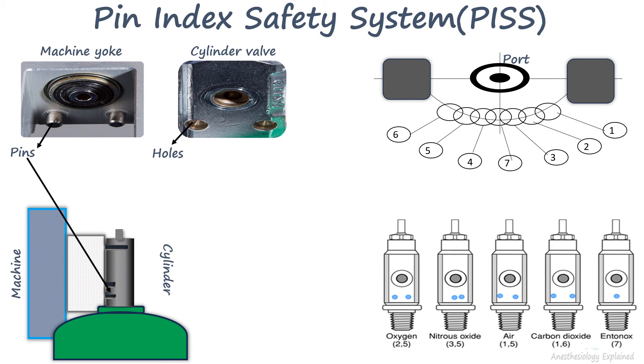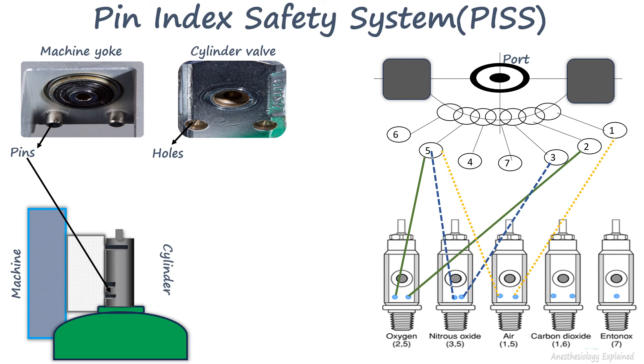The positioning of the holes utilizes an arc of a circle centered around the port, with seven hole positions equally spaced along it. Various combinations of these holes are chosen for different gases, and the corresponding pins on the hanger yoke are precisely designed to fit into these holes. For example, oxygen is identified by the pin index of 2 and 5, nitrous oxide by 3 and 5, and medical air by 1 and 5. Entonox is distinguished by having only the hole numbered 7, which aligns vertically beneath the center of the port.